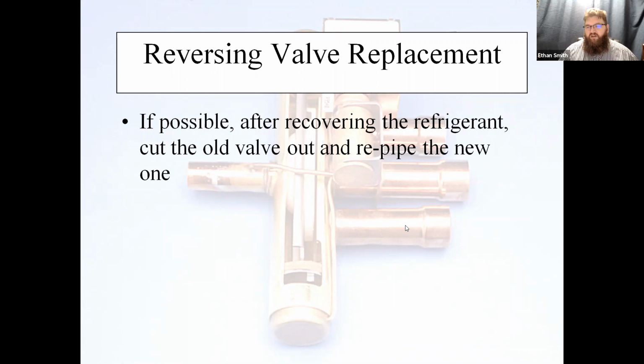So changing out reversing valves, they're really hard to braze in and out, guys. What I generally recommend is you get yourself a little stubby pipe cutter, and after you recover the refrigerant, cut the old valve out. Do not try to unbraze it. It's just going to be miserable. And then repipe the new valve in and use repair couplings. So we would actually take these stubs and cut them downstream somewhere where it's easy to get the cutter on and it's easy to weld. It's typically very difficult to weld up at these points.